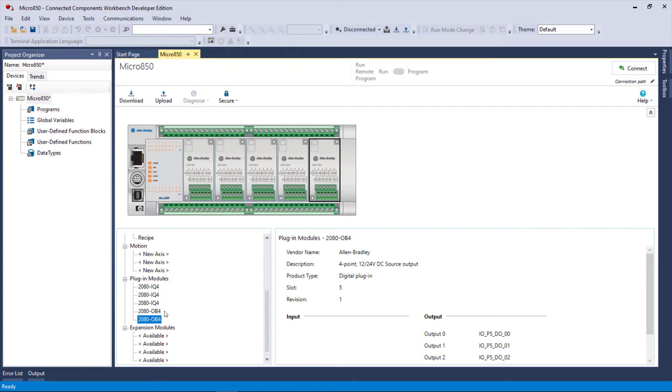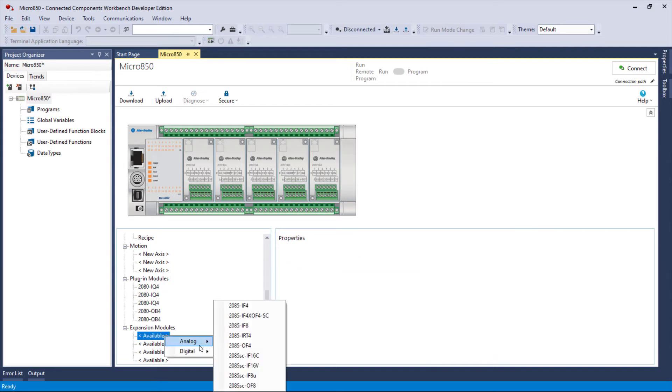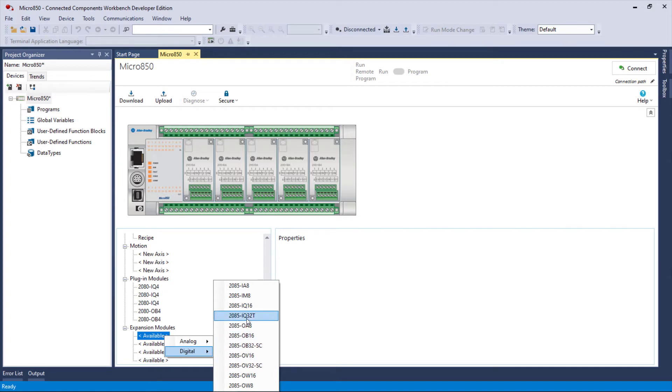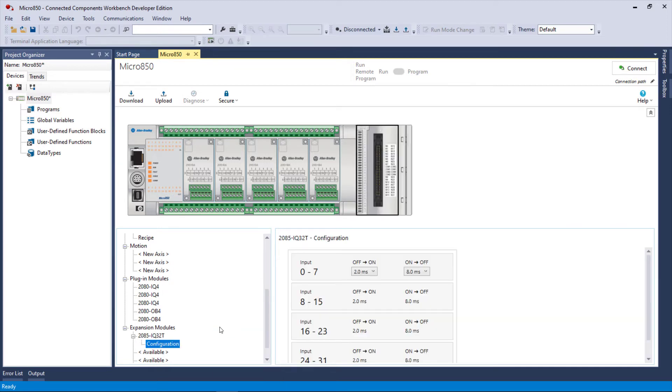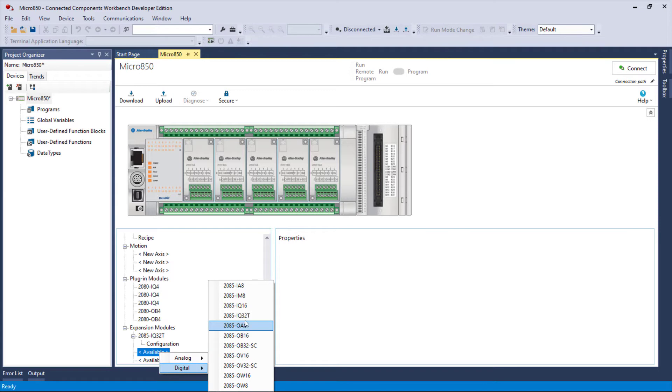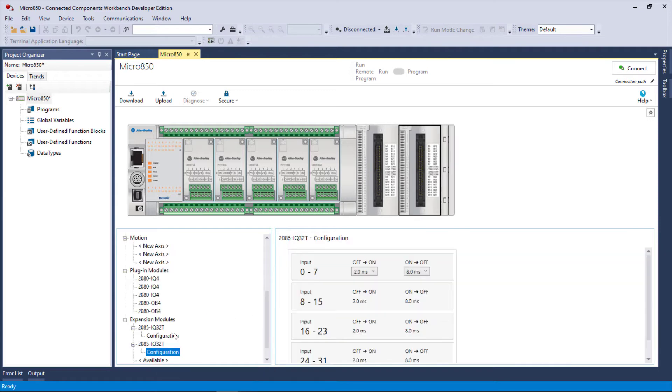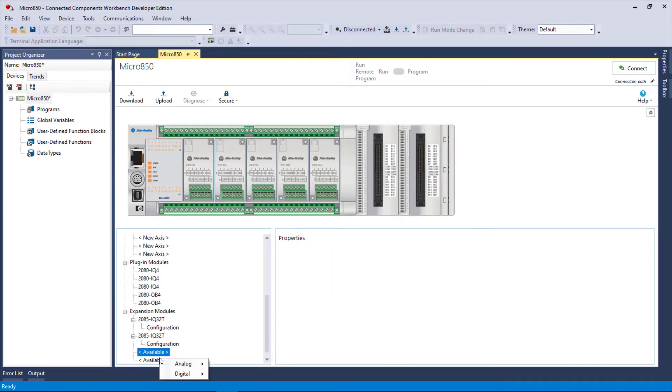So we have a total of 20 IO here: we have 12 inputs and 8 outputs, all DC. Expansion modules, we can do the same thing, however it will accept 16 and 32 bit. So I'm going to go with a 32-bit input, another 32-bit input, and then another 32-bit output and a 32-bit output.